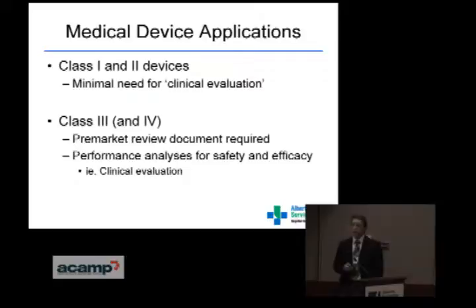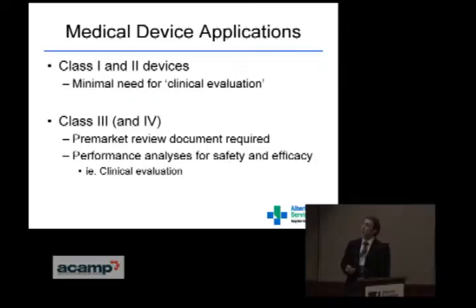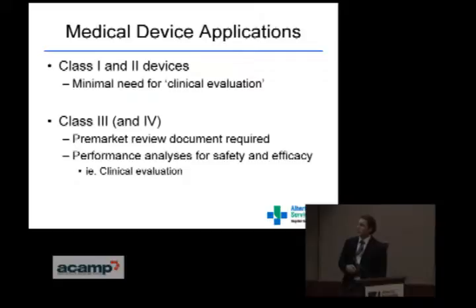As a matter of definition, when talking about medical device applications, Health Canada categorizes things in four classes. Class one and two medical devices really don't need a whole lot of clinical evaluation as far as Health Canada is concerned, though that may be a bit overgeneralized for some class two devices. For today, we're really talking about class three devices from a diagnostic perspective — and four as well — but these are the devices that require quite sophisticated pre-market review documentation for a Health Canada application. In easy terms, this is a clinical evaluation of safety and efficacy.